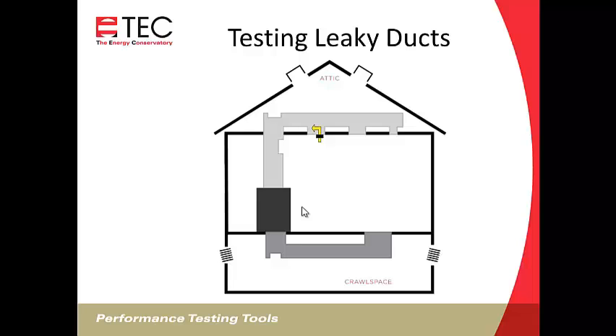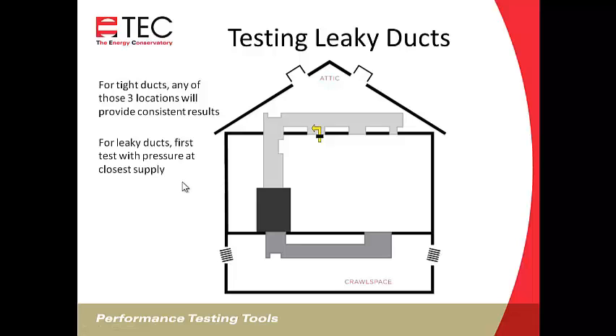But when we're testing leaky ducts, we recommend that you do two tests. That you do one test measuring pressure at the closest supply, and then move it to the supply that's farthest away, and take your next test there, and then average those two numbers. So that'll give you a more representative number, because if you think about leaky supply ducts, the farther you get down the line, the more it's bleeding off air, and you can see a different pressure at the far end than you'd see at the near end. So that's why I recommend, if you're testing leaky ducts, to do your test that way.